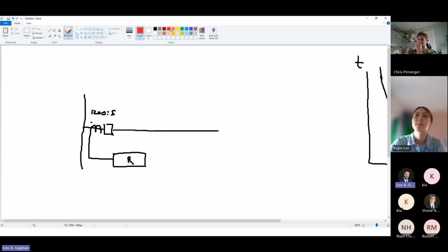As your fault gets further and further away from your relay, you've got this line impedance. And the further you get away, the more line impedance will reduce that fault current. So a fault right here could be 5,000 amps. You get a little further away, it could be 4,000. You get a little further away, it could be 3.